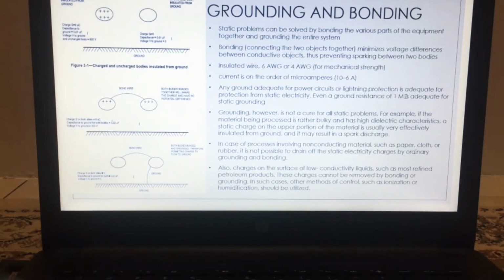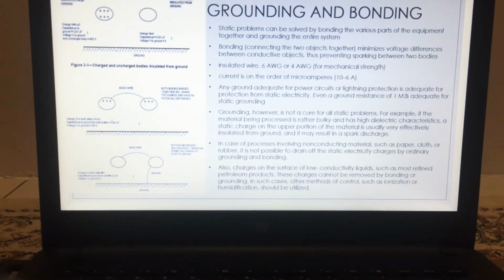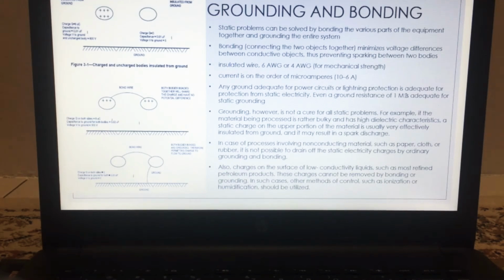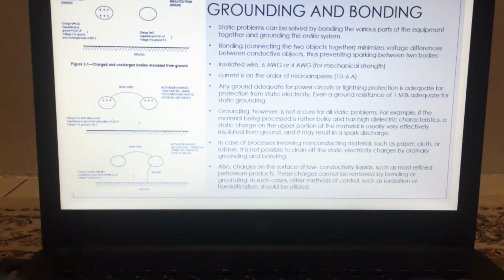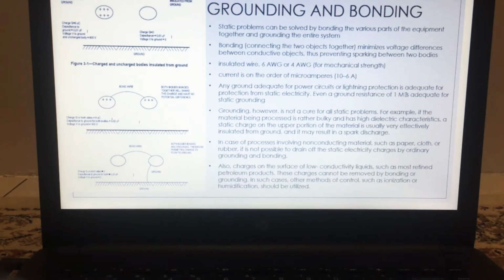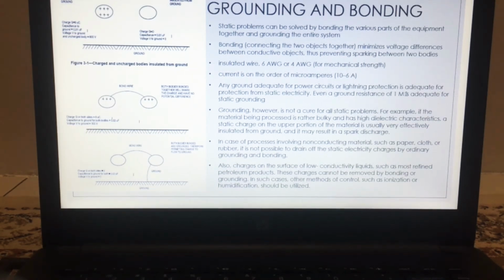Any ground adequate for power circuit or lightning protection is adequate for protection from static electricity. Even a ground resistance of 1 megaohm is adequate for static grounding. Grounding, however, is not a cure for all static problems. For example, if the material being processed is rather bulky and has a high dielectric characteristic, a static charge on the upper portion of the material is usually very effectively insulated from the ground, and it may result in a spark discharge.